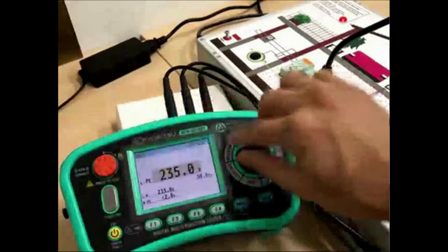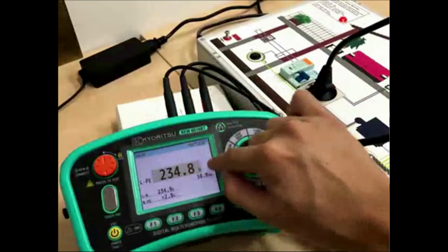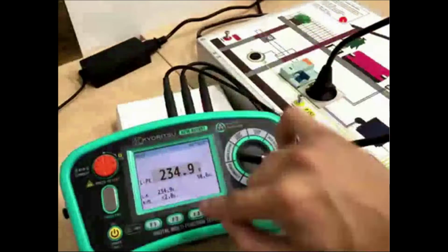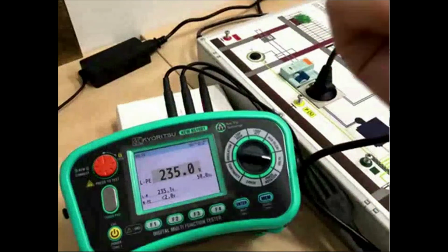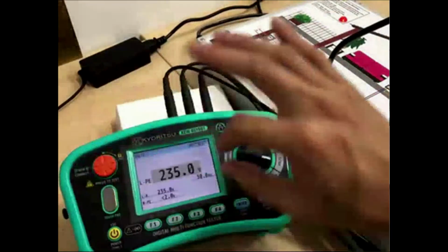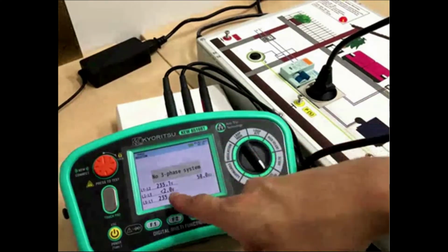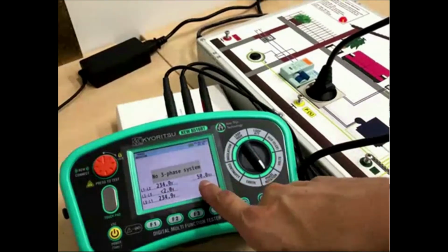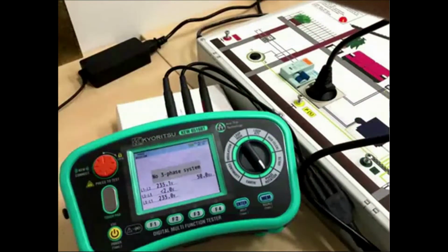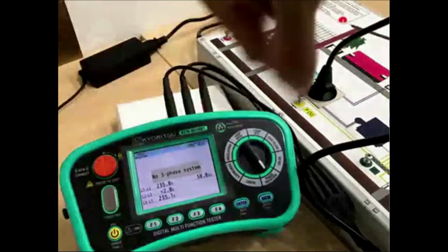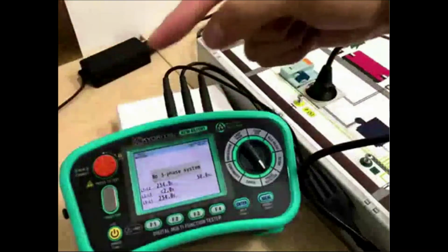Now this is to show the voltage of each line. Live to PE, potential difference; live to N, potential difference is this; N to PE, potential difference is this. Now phase rotation: we don't have a 3-phase system here, sorry, I cannot show you. As I mentioned in my PowerPoint slide, when green 1, 2, 3, your phase sequence is correct. When red 2, 3, 2, 1, your sequence is the other way around.